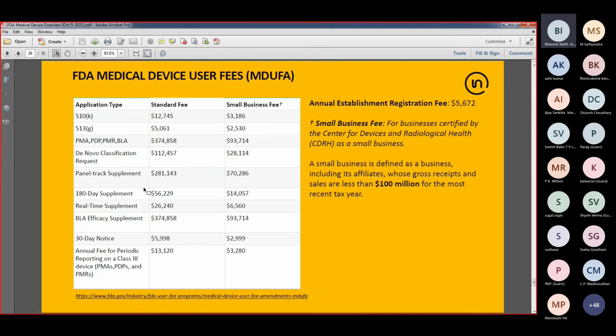PMA is the most time consuming and stringent submission, but its cost is also substantially higher compared to the 510K, as you can see here, where you're looking at over $12,000 as a standard fee. You're looking at De Novo, almost 100K more. And when you go to PMA, you're looking at over $350,000. So be very mindful of these fees that the FDA is charging.